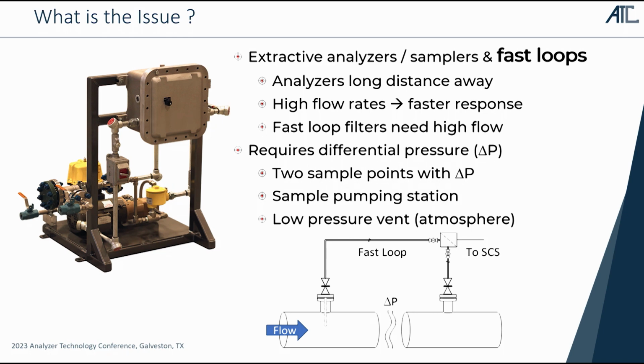If you look at that figure at the bottom, you can see if we have a direction of flow, some differential pressure, a high pressure point and a low pressure point, it's pretty easy to get continuous flow through this loop. But it's going to require some differential pressure. That usually means we're either going to have process differential pressure available, or we're going to have to put in something like a sample pump, or put in a low pressure vent, venting to a flare header or maybe atmosphere. We'd like to find a way to create fast loops without having to meet all those requirements.